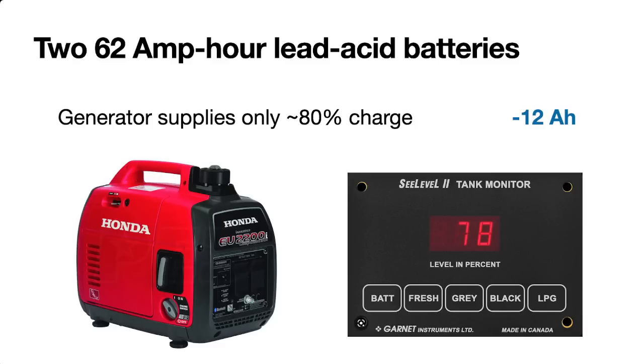So here's the other problem. Lance is charging with the generator. Now he says he's running that generator 5 to 7 hours. If he runs it for maybe 8 to 10 hours, he's probably going to get those batteries to full charge. But most people don't do that. They run the generator 2 or 3 hours. It looks like the batteries are full, but they're really not. The reason is that the last 20%, getting from 80% to 100% full, takes a long time, many hours. If you run it for about 3 hours, you're only going to get to about 80% of charge at best, even though it may look fully charged.